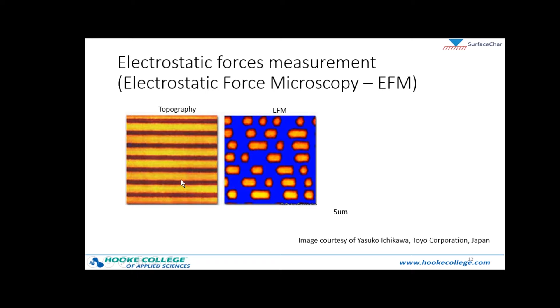Here's an example of amorphous bits on a DVD-RW. This is a topography image, and the EFM image on the right clearly exposes the amorphous bits formed, which are not seen at all in the topography image. A magnetic analog to EFM to probe magnetic properties is known as magnetic force microscopy, or MFM. Cantilevers with a magnetic coating can be used for this mode. In this mode, like in EFM, a cantilever is lifted over the sample, and the tip-sample magnetic interactions are detected and used to reconstruct the magnetic structure of the sample.